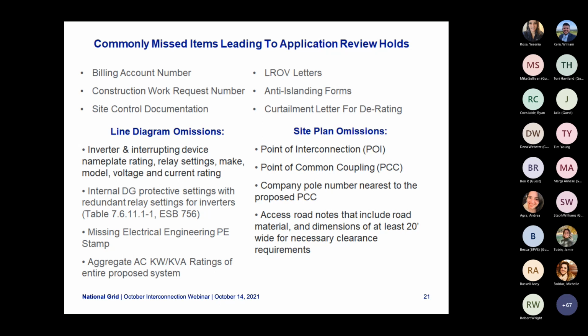Some of the things we see missing on one-lines are the inverter and interrupting device nameplate rating, relay settings, and the same with the DG protective device settings. One-lines also sometimes won't have a PE stamp from an electrical engineer.